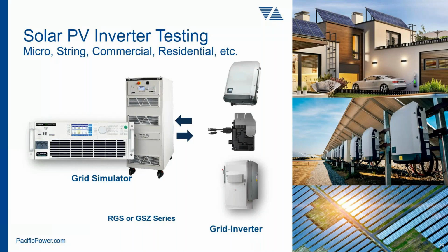They come in power levels as small as microinverters, maybe as much as 200, 300 watts per panel, to string inverters that generally are used for home solar installations, or larger systems for industrial solar installations. So the power range can be from a few hundred watts to megawatts. It's a huge spread that is covered by that, so you obviously have to size your grid simulator accordingly. A smaller rack mount form factor like you see on the left is convenient for lower power applications, starting at maybe 12 kilowatts and up. A cabinet type system, a higher power system, can be better for larger inverters. So it just depends on what size of products you tend to use.